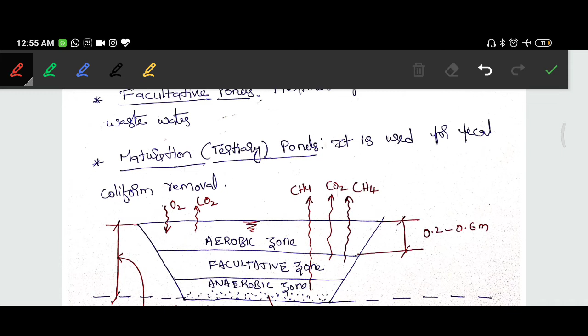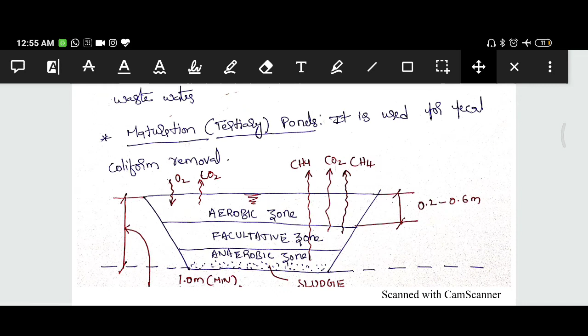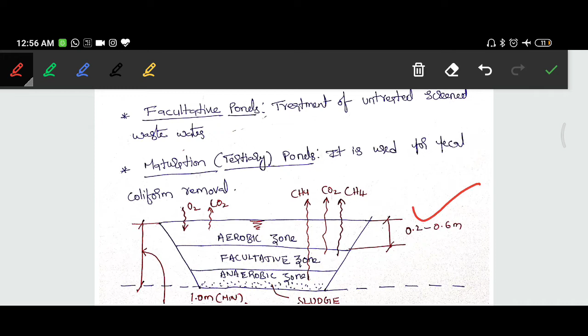So let's see with a picture here, you can understand easily. The first zone will be the aerobic zone, then the second zone will be the facultative zone, and the last one is the anaerobic zone. The aerobic bacteria will take oxygen and release carbon dioxide. From the facultative zone, it will release carbon dioxide as well as methane. In anaerobic, it will release methane. As per the design, the maximum height of this pond we can take as 1.5 meters. Minimum we can take 1 meter. Each zone has 0.2 to 0.6 meters.